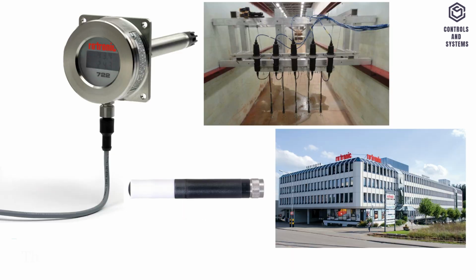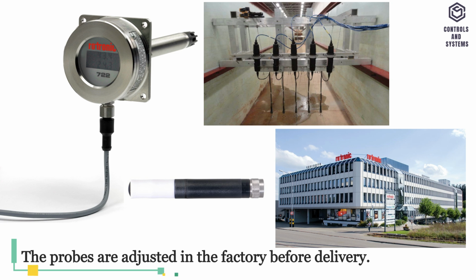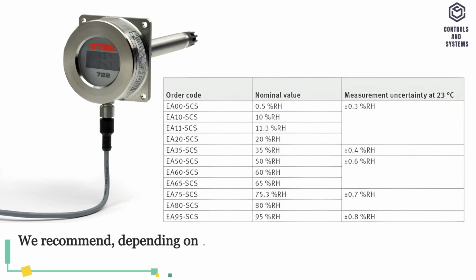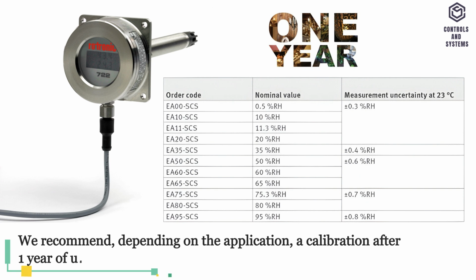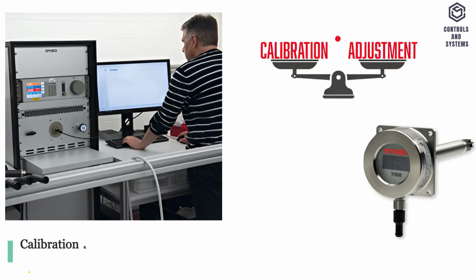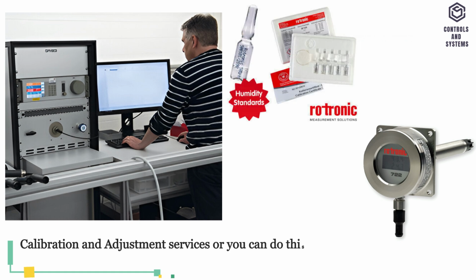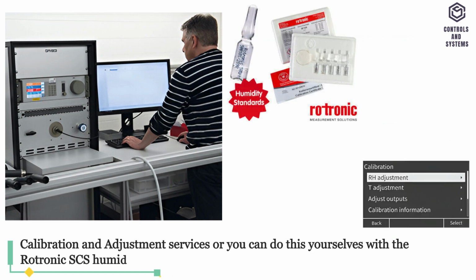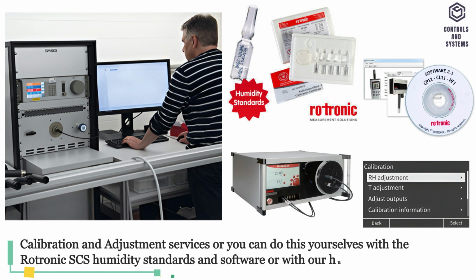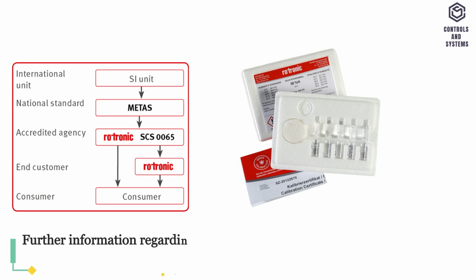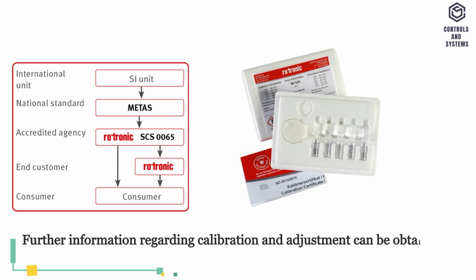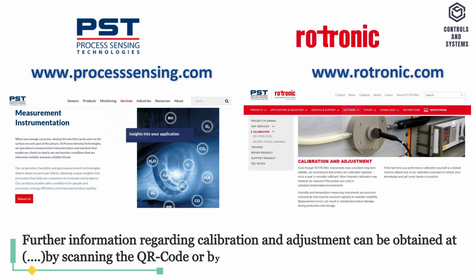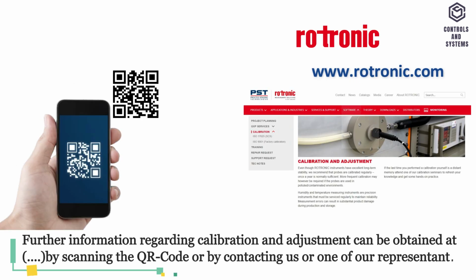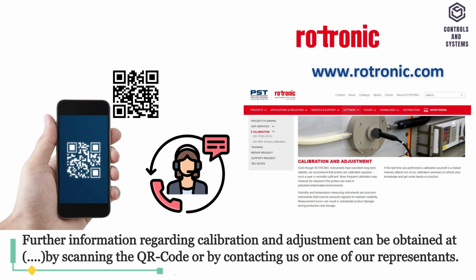Calibration process. The probes are adjusted in the factory before delivery. Depending on the application, a calibration after 1 year of use, and calibration and adjustment services are available. You can perform this yourself using the Rotronic SCS humidity standards and software, or using humidity generators. Further information regarding calibration and adjustment can be obtained at processsensing.com or rotronic.com, by scanning the QR code or by contacting us or one of our representatives.